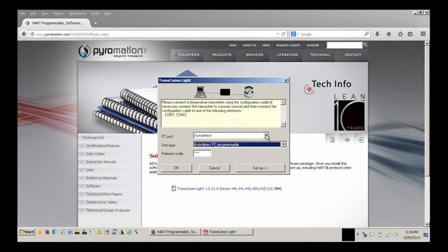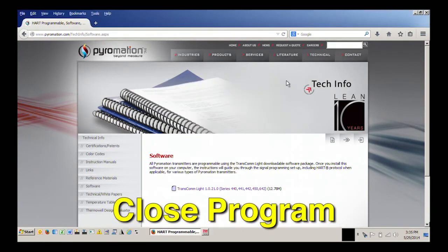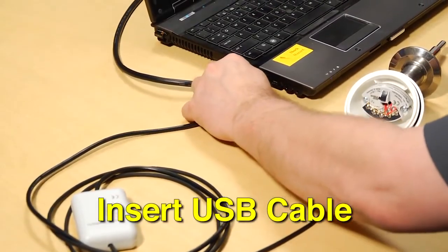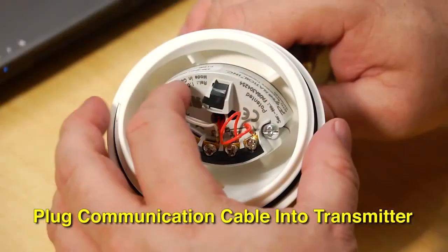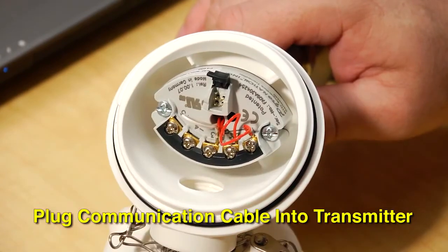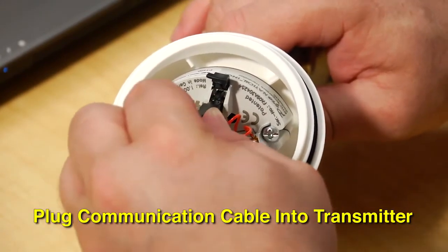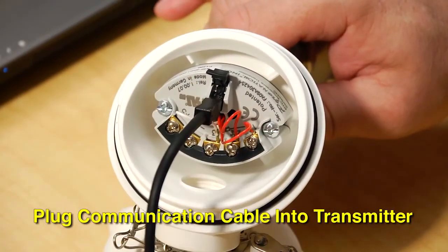It comes up with Auto Detect and Auto Detect PC Programmable. You want to look and see which COM ports are available. Then the trick is to close the program, insert the USB into the computer, plug in the communication cable into the transmitter by opening the access door right on the front of it.